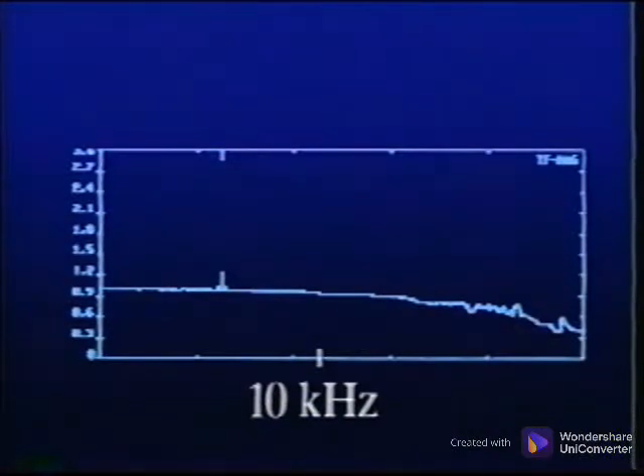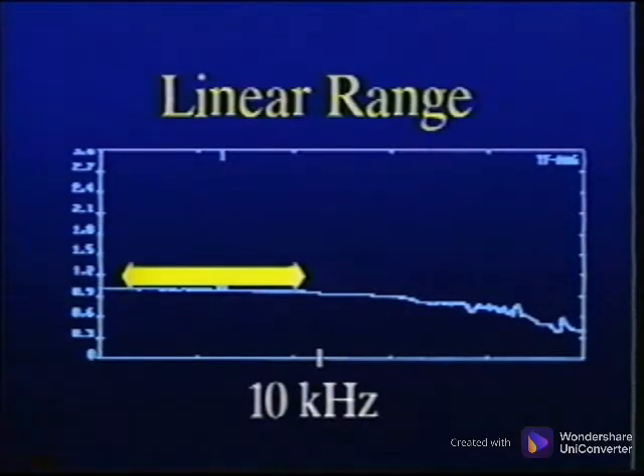This spectrum from a sensor mounted on a shaker table shows its linear or stable frequency range to be from approximately 2 Hz to 10,000 Hz. Frequencies below 2 Hz or above 10,000 Hz would not be accurate in amplitude. Another sensor must be used that is linear in those ranges for amplitude accuracy.